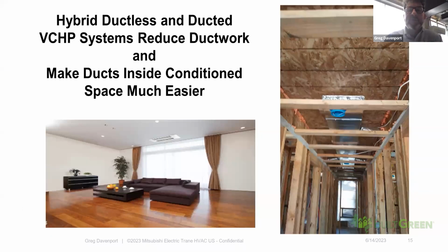So this is a little different approach that I think will work well for some builders. You can see over here—that's the one-way cassette. If you put that in the great room, you can eliminate a ton of ductwork in a home. On the right side of this image, you can see what we call a slim duct system—about 20 or 25 feet of little trunk line in a soffit ceiling serving all the bedrooms in this Rambler house, with little branches going into each of the small rooms.